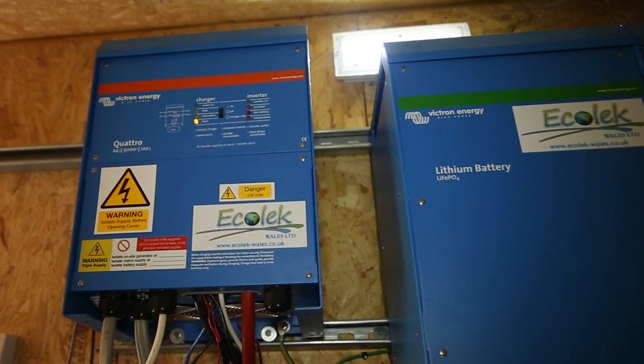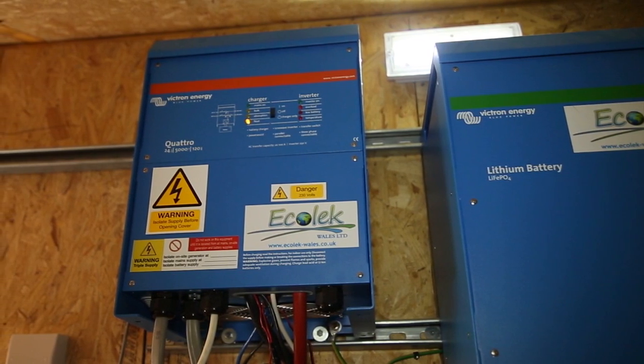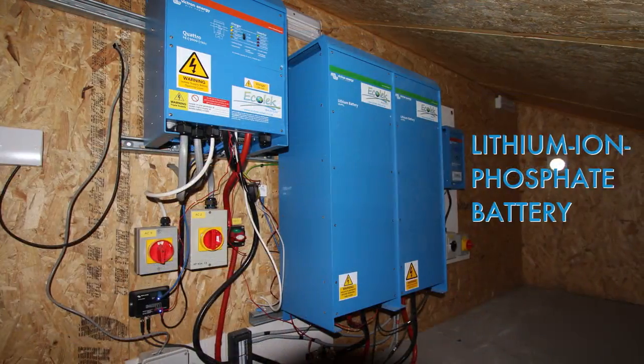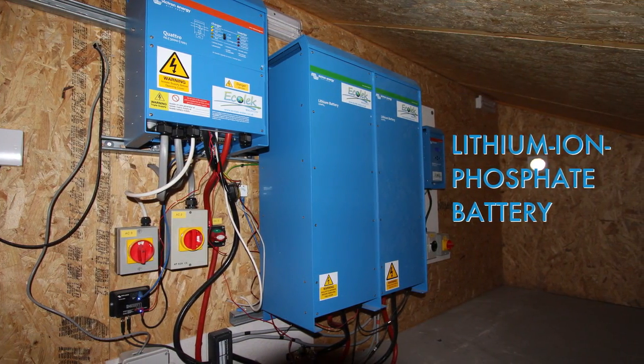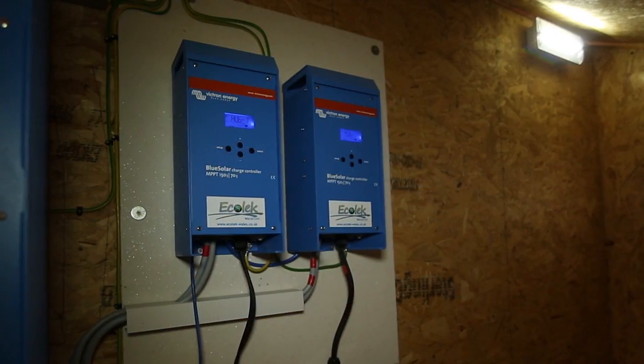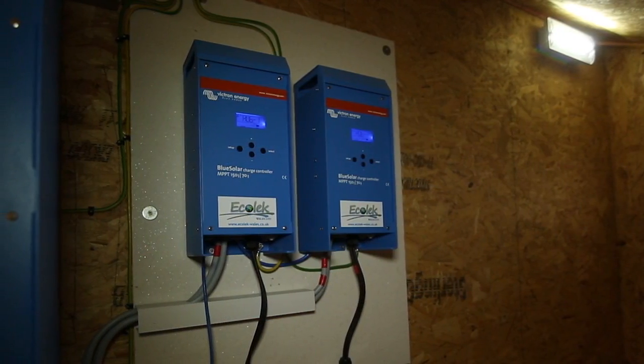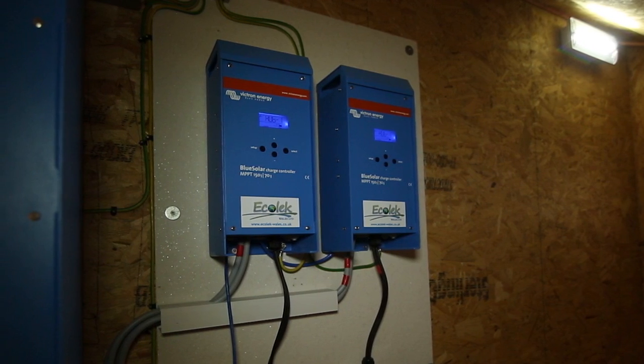The PV array feeds via 8 strings into a DC fuse board where we concentrate the amperage. From there it's fed through to 2 70 amp battery chargers, which is why it's so different to a standard setup. This enables us to charge the batteries far quicker on days where the irradiation could be quite variable.